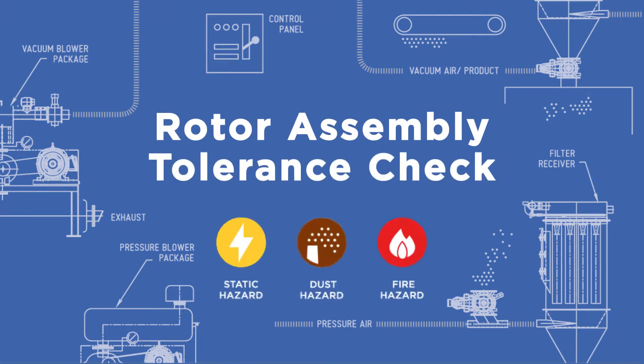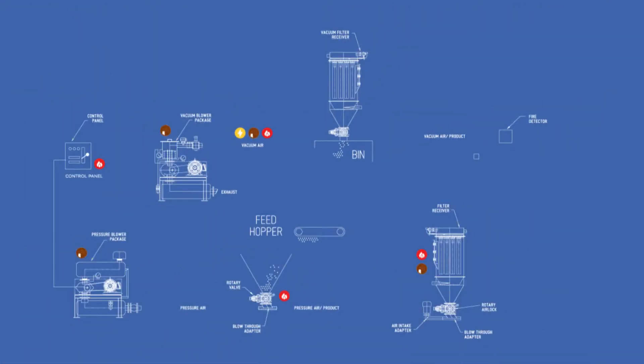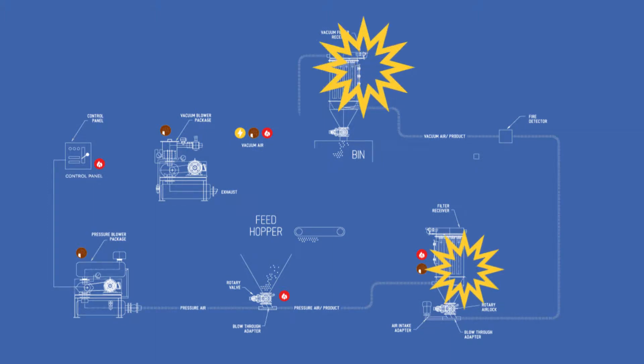The rotor assembly is at the heart of the rotary valve. It acts as an airlock for the pressure difference between what is above the valve and what is below the valve. If a rotary valve is compliant with NFPA, it can help reduce the passage of flames along a conveying line should an explosion happen. The following video outlines what those compliance rules are, as well as how to test your rotor tolerances.